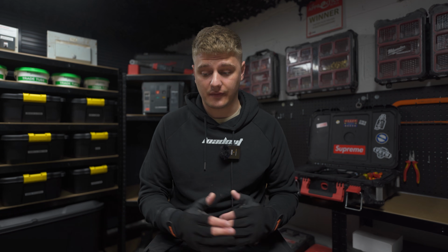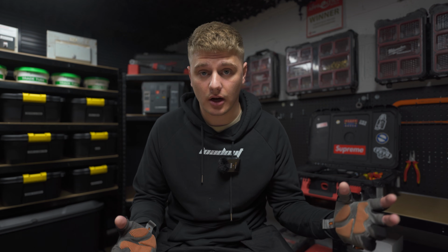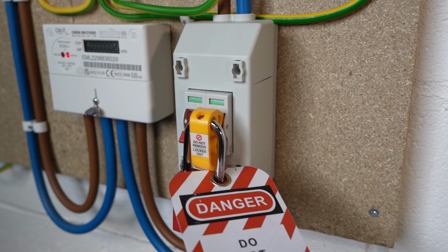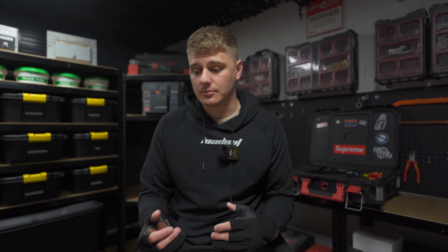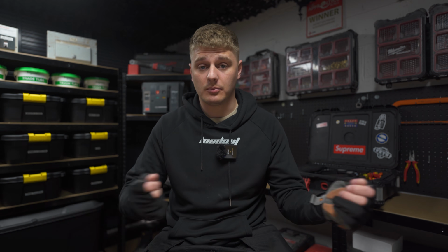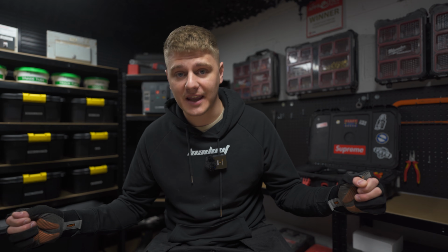However, on existing or live installations, of course, it is already energized, and you need to verify the continuity of them to carry out an EICR, right? So you need to isolate the installation completely, because part of the testing process is going to involve you potentially removing some of the bonds, and as we've just gone through in the theory, without the bonds in place, you've got that potential difference there, and of course you'll actually be touching both parts potentially at the same time.